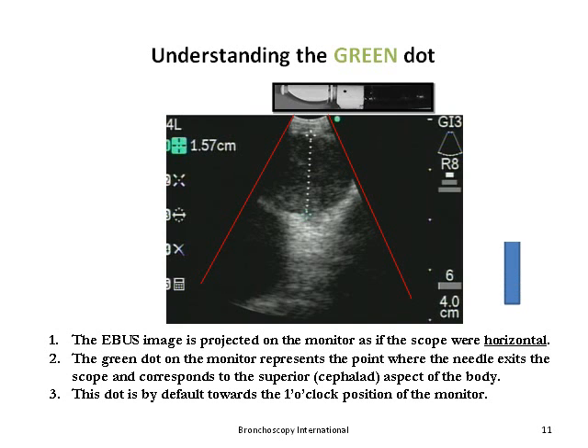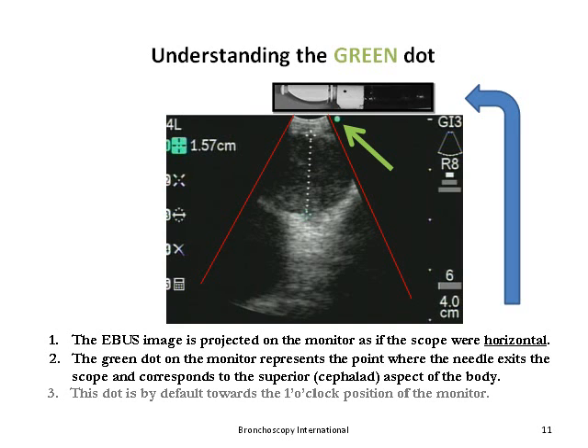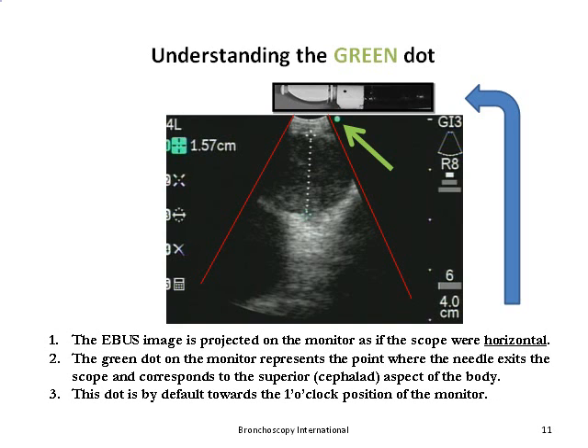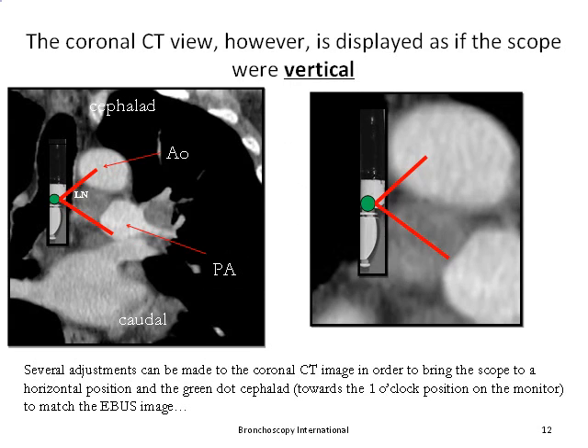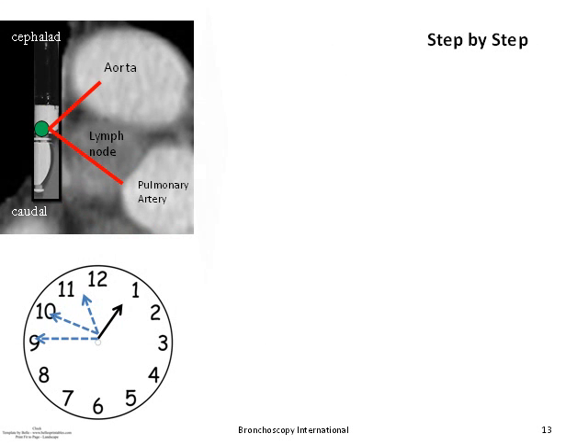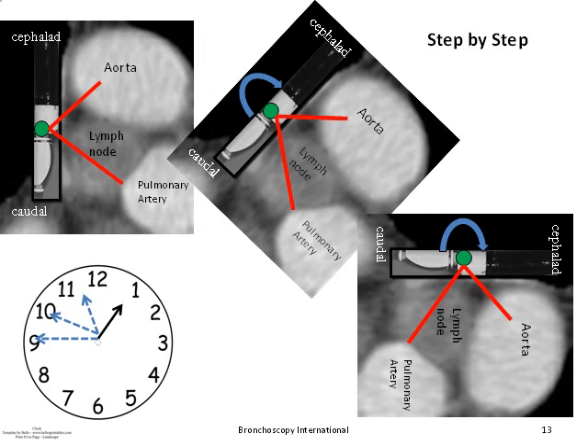The EBUS image is projected on the monitor as if the scope were horizontal. The green dot on the monitor represents the point where the needle exits the scope, which corresponds to the cephalad aspect of the body. This dot is by default towards the 1 o'clock position on the monitor. Several adjustments can be made to the coronal CT image in order to bring the scope to a horizontal position and the green dot cephalad to match the EBUS image — rotate the CT image clockwise to bring the scope to a horizontal position and the green dot towards 1 o'clock.